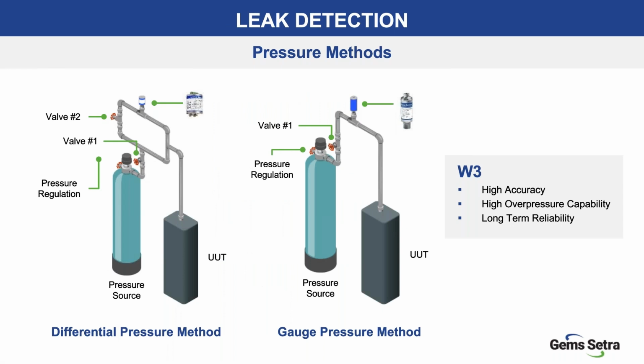Next application I want to discuss is leak detection. Very common. However, in certain applications, there is a need for very high accuracy to enable customers to confirm their system's performance under the smallest leaks versus the largest leaks. Here we have a diagram of the differential pressure method of measuring leaks between the unit under test and the pressure source on the left side. There we would incorporate the ASM product for support for this.